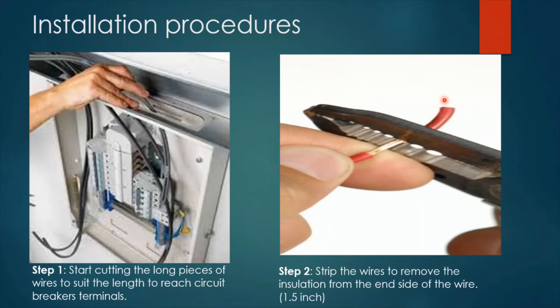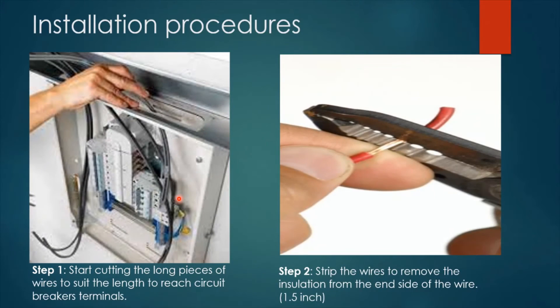Now let's look at the installation procedures of wire termination and dressing. Step one is to start cutting the long pieces of wires to suit the length needed to reach the circuit breaker terminals. As you can see, the wires are cut to a specific length to exactly meet the terminal of the circuit breaker. Step two is to strip the wires to remove the insulation using the wire stripper. It is recommended to remove 1.5 inches or around 4 centimeters of insulation.